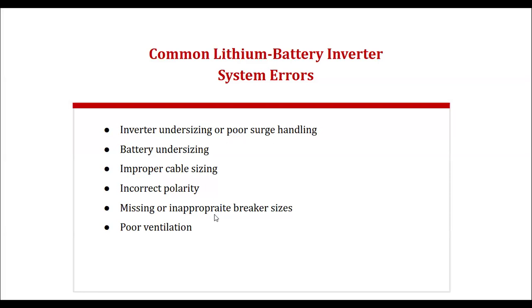Missing or inappropriate breaker size. Two things will happen when you inappropriately size a breaker. Either the capacity of the breaker is higher, allowing higher current to flow when it's supposed to trip off. Then what are you protecting? For instance, you have an inverter that you're supposed to protect with 20 amps. You go and put 100 amps or 150 amps. Then it's as if you are not protecting anything. So you are stressing the inverter up. The inverter will now be the one doing the protection by itself.